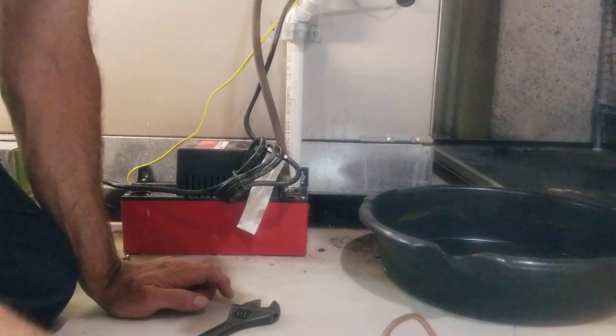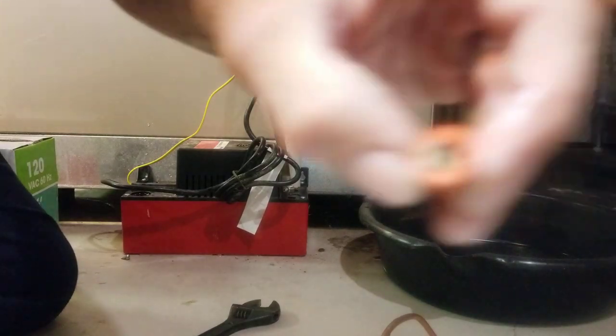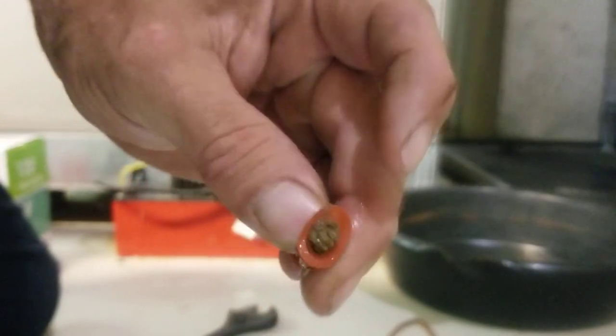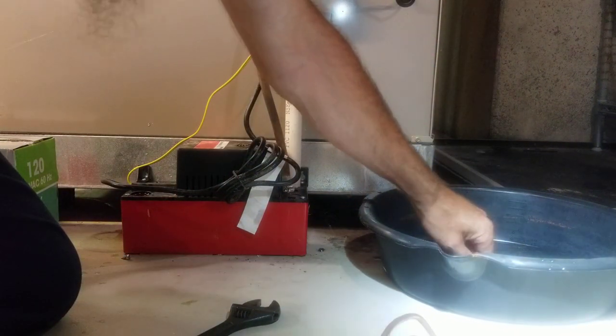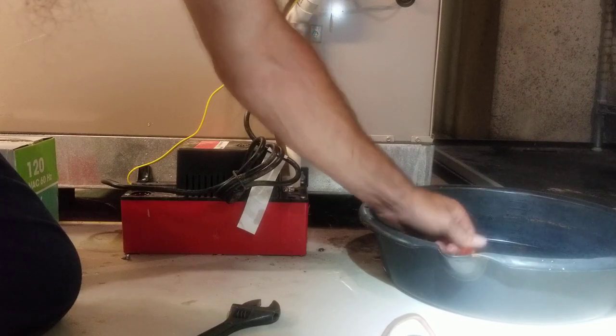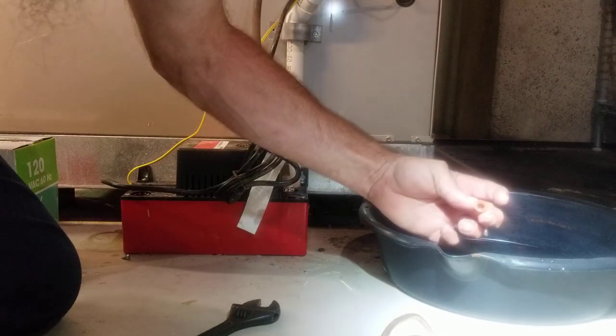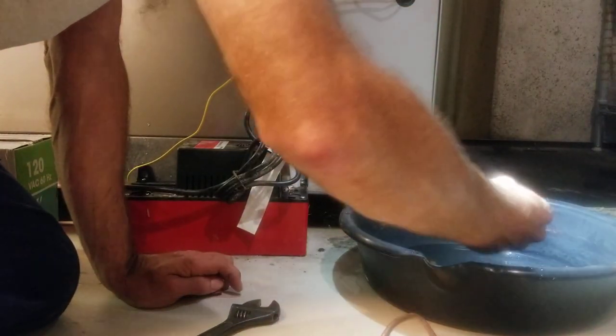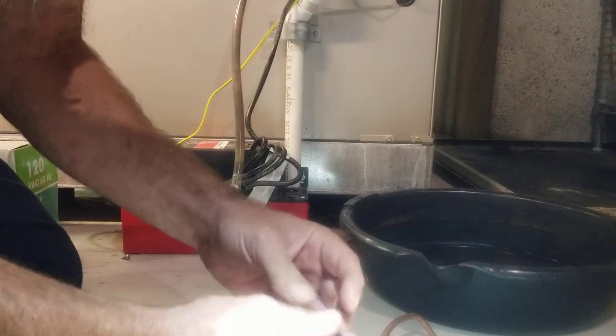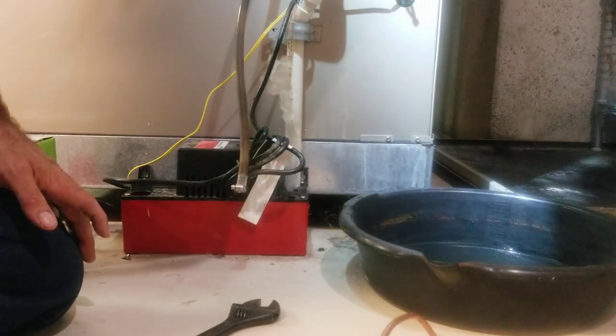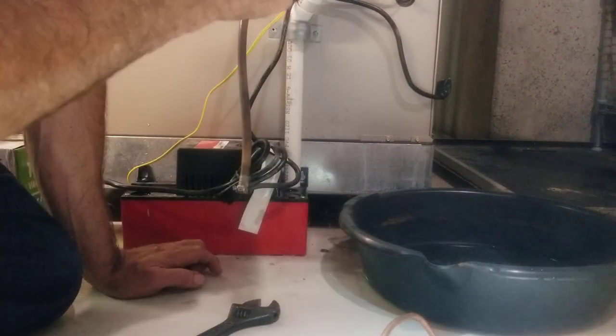Oh look at that, a bunch of garbage in the check valve. I don't know if you can see that. I blew the line out. I was ready to change the pump. Let's stick this back in here. Oh look at that, clogged check valve.